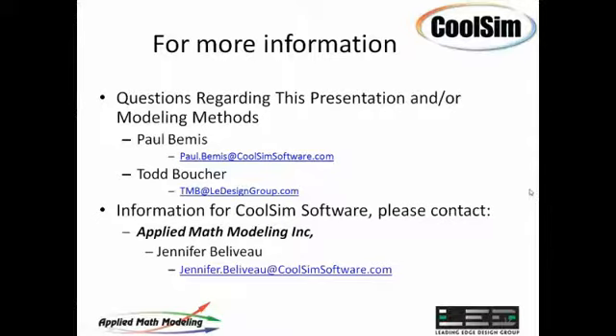So I guess the long and short of it is that we do design still to, and we recommend still, the ASHRAE 80.6 Fahrenheit max intake temperature, because if you can get it there, then you're fine. If you can convince your operational people to run higher than that, good. But Todd, I think you'll agree, we've struggled to get people up to 70 degrees from 55 degrees in these data centers, right? Oh, yeah, absolutely.